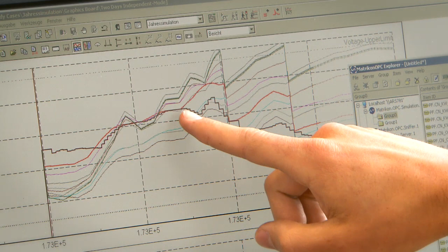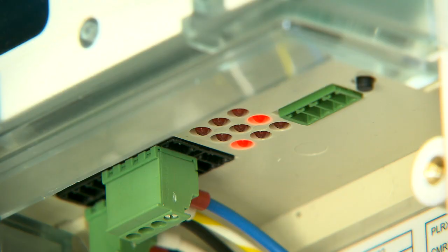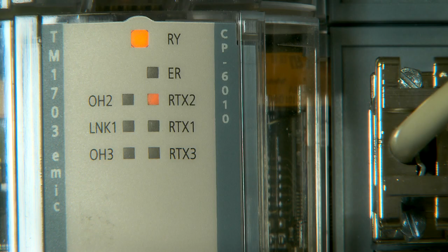To verify whether the technology can be used in other rural regions as well, another test system was set up in the region of Salzburg. Its core is a central processor located in the System Control Center in Bregenz, called the Central Voltage Control Unit, CVCU. At various critical nodes of the test system in the Großes Walsertal, 16 points of measurement were installed. These continuously provide the control center with the latest data.